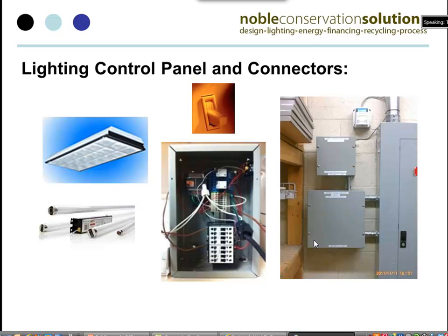We also control lighting. In addition to the rooftop units, we put in essentially very sophisticated switches, so we can help our clients turn the lights off when they're no longer in their stores. We've had situations where we've come into stores and found that they run their heating and cooling at the same level 24 hours a day, 365 days a year, and they happen to be in an environment in Texas that gets extremely hot. It can be 110 outside, and they come to the back office that nobody's in the middle of the night at 68 degrees, and they're running cooling to maintain that.